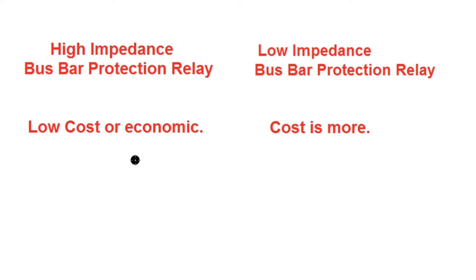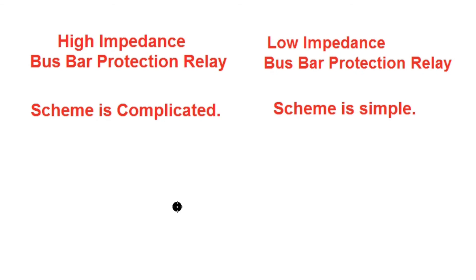In case of high impedance bus bar protection relay, although the scheme is complicated, it is low cost or economical in budget. In case of low impedance bus bar protection relay, the budget is more, or it is more cost-intensive. The high impedance scheme is complicated due to the requirement of stabilizing resistance calculation, Metrosil, and CT switching relay — all of which make the scheme somewhat complicated.